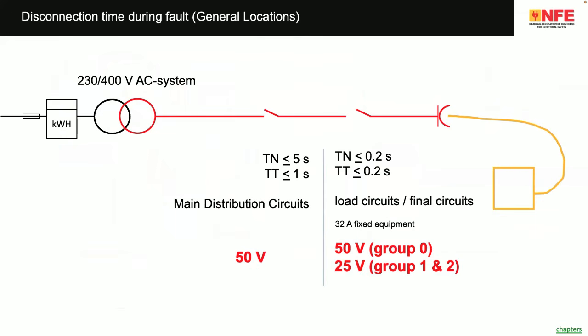Disconnection times are defined in the National Electrical Code. We have very clearly mentioned the disconnection time, for example, at the main distribution circuits, final distribution circuits. So the disconnection times, for example: TN system less than or equal to 5 seconds, the TT system 0.2 seconds. The most important point is the disconnection time is specified. Now you must ensure that your protective device is able to trip within this particular time. And if the device is not tripping, hazard happens. Most of the electrical fire accidents, if we study in detail, you can understand that the protective devices are not tripping. If the protective devices are tripping, then a lot of accidents can be reduced.